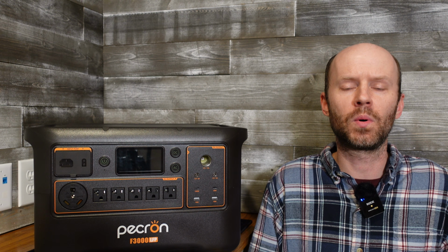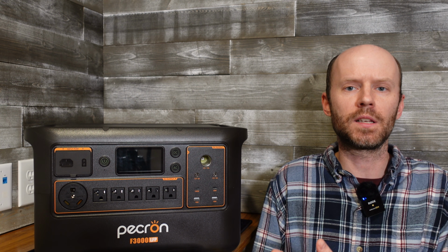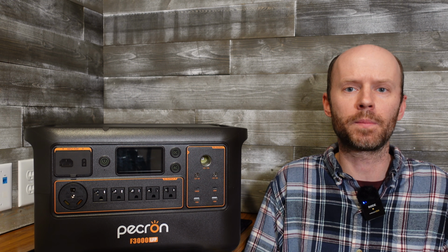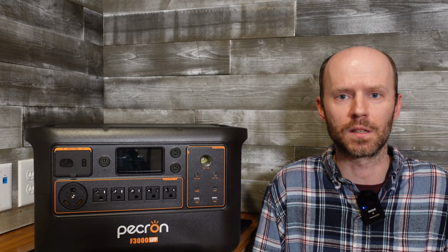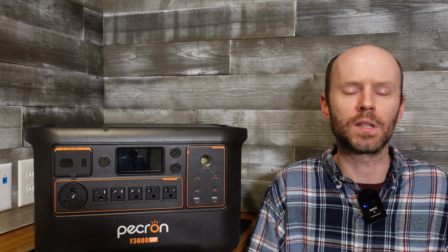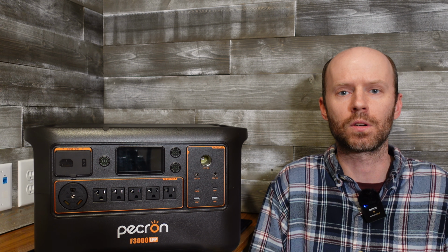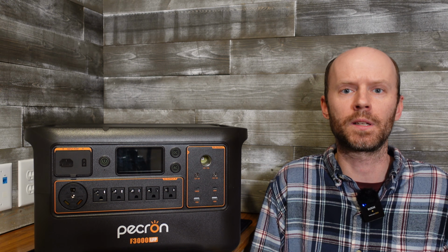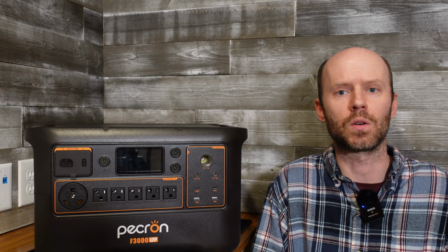There are a few additional points to discuss. When using this as a UPS, the transfer time from grid to battery power could be up to 20 milliseconds. For that reason, I would not recommend using this as a UPS for a computer or a server. With computer equipment, we typically like to see transfer times of 10 milliseconds or less.